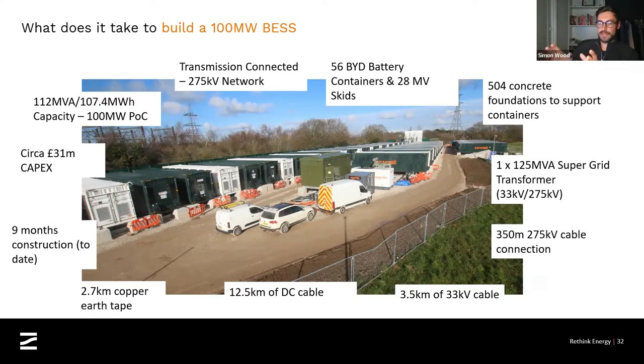I'd love to show you a picture of inside one of these containers, but unfortunately we're not allowed. But there's a lot going on in there, and we get these pre-assembled, and that's what allows us to build these sites in such a short amount of time. It's very modular in nature. The white containers that you can see there are actually a skid, a package system. We refer to these as the MV skids, and they basically house the inverters that Mike was just talking about. There are five inverters on one of those white skids. It also includes the transformer that steps the voltage up, in this instance from 400 volts to 33 kV. And then there's the RMU, the ring main unit, which forms the point of isolation and connects all of the MV skids together for that circuit.